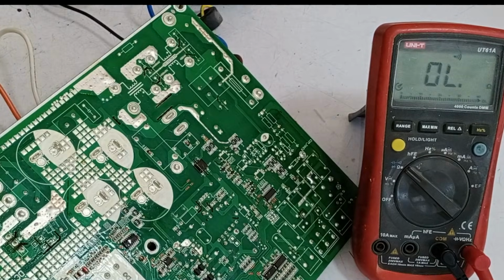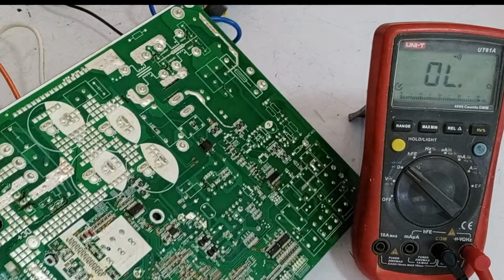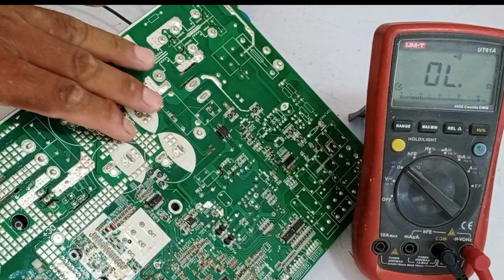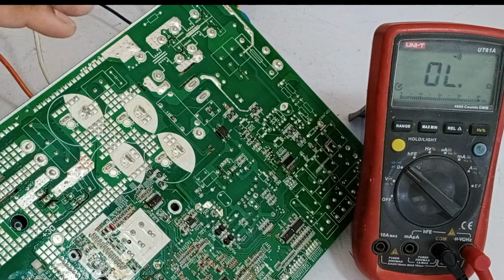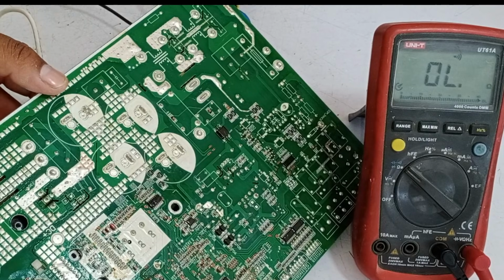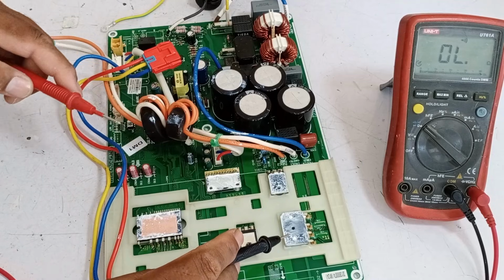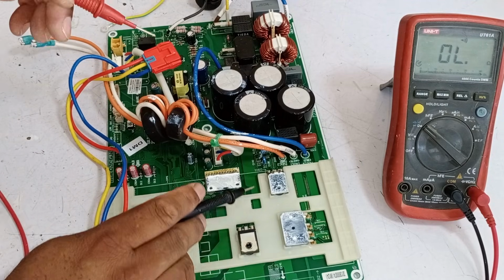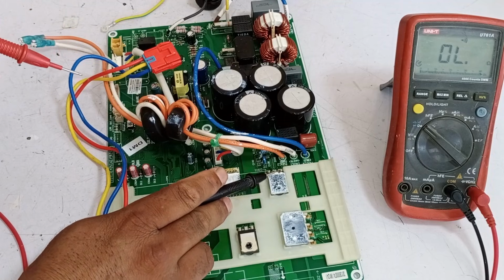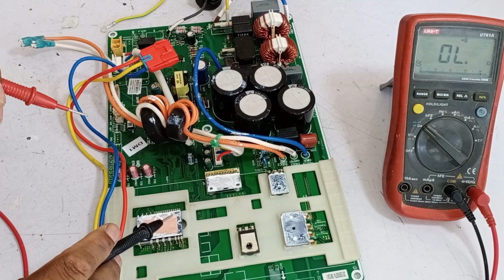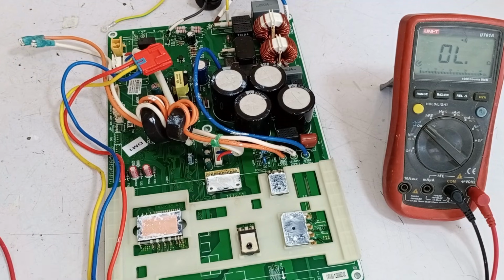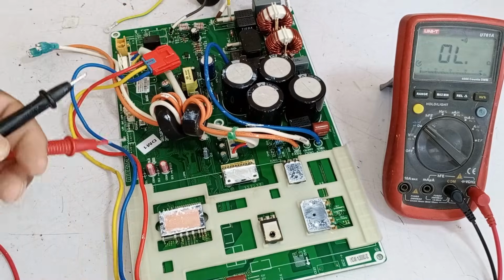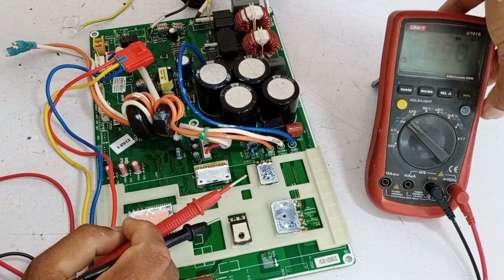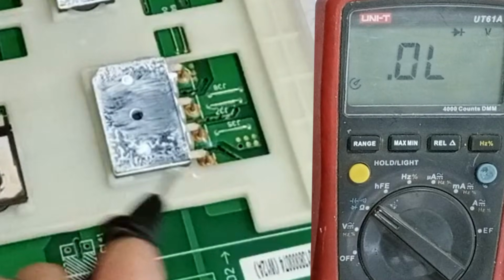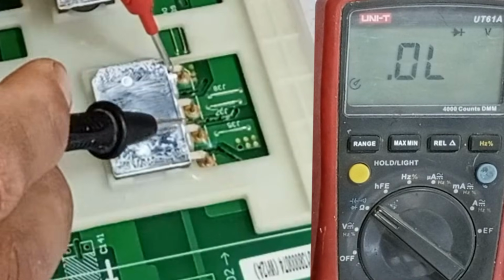Now we need to identify what's causing the problem on the high side. If these capacitors are shorted, they will need to be removed. But before removing them, let's test the other components. The main bridge rectifier, if shorted, could also cause this issue. Additionally, the diode, IGBT, and IPM could be faulty or short-circuited as well. So first, I'll check the rectifier. I'll set the multimeter to diode mode. The red probe is placed on the positive pin, and the black probe is on the negative pin.